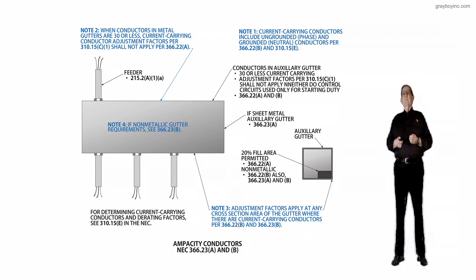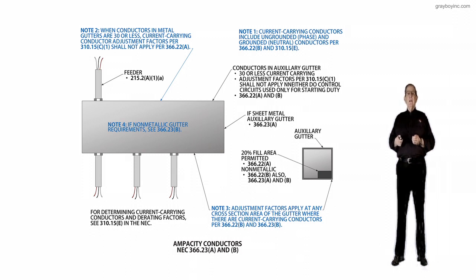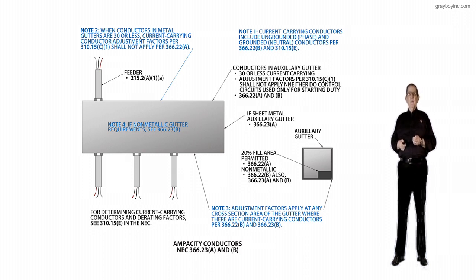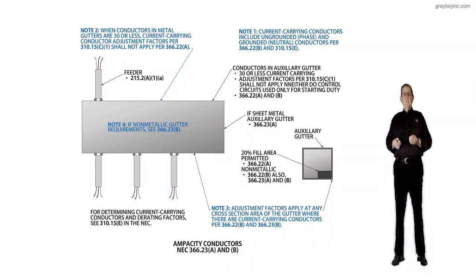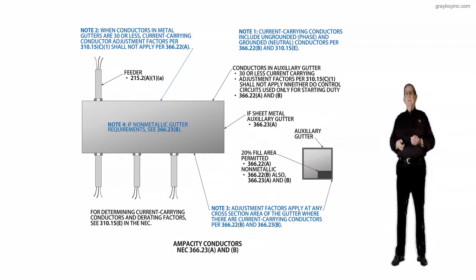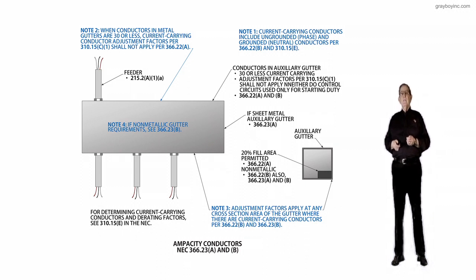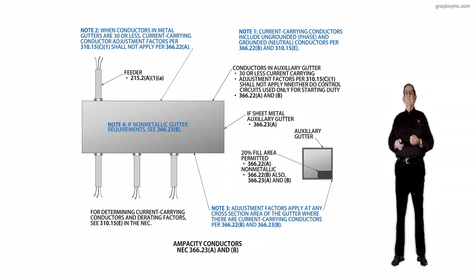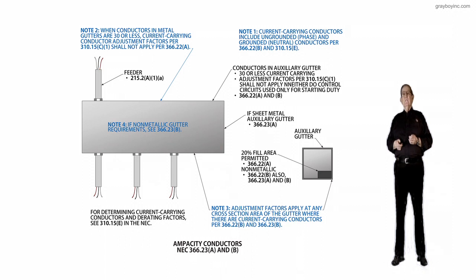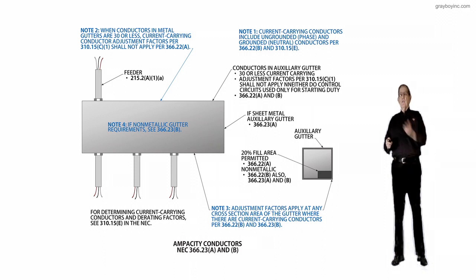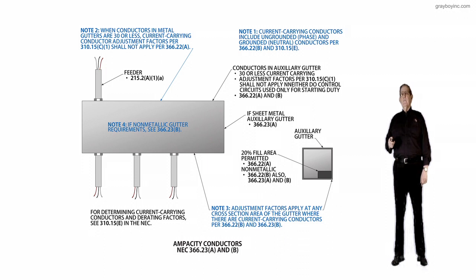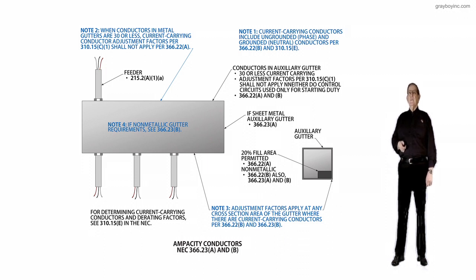And then, of course, we know that this is outlined in 366.22A and B mainly. Now, the third thing I'd like to point out is right below the conduits that are nippled out of the auxiliary gutter at the bottom, and it says for determining current carrying conductors and derating factors, we'd see 310.15E in the NEC for these regulations.